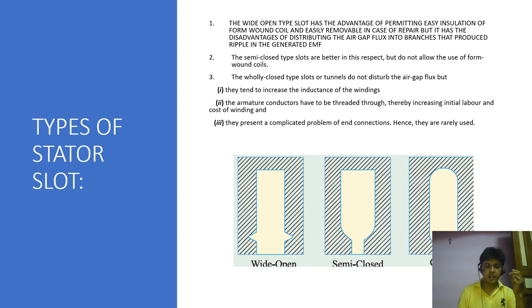So we are now going to discuss about how many type of stator slot is used. The first one is wide open type slot, second one is semi-closed type slot, and third one is fully closed type slot. In fully closed type slot, that tends to increase the inductance of the winding. The armature conductor have to be threaded through, thereby increasing the initial labor and cost of the winding. They present a complicated problem of end connection. Hence they are rarely used.